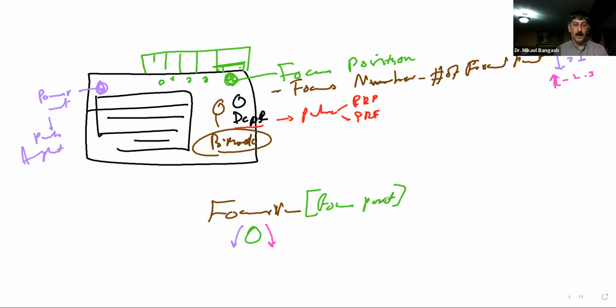So what I told you was, how do we switch it around so that this knob is not adjusting the number of focal points, but instead we can physically move them to shallower depths or deeper depths as well. You just press on it and it will flip. Whatever was outside the bracket is now shifted inside the bracket, and what was inside the bracket now becomes outside the bracket. So we have focus position, and then focus, which is the number of focal points, written inside the bracket.